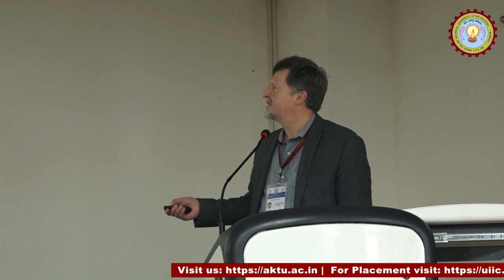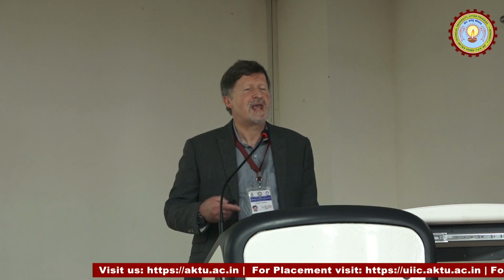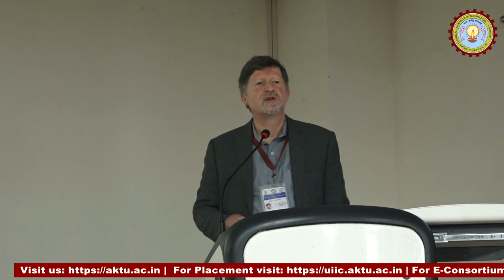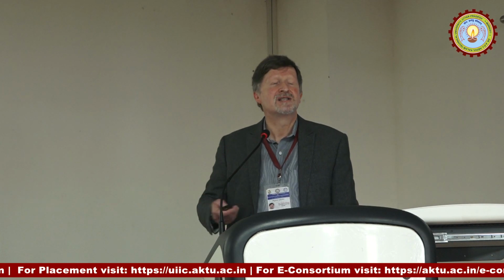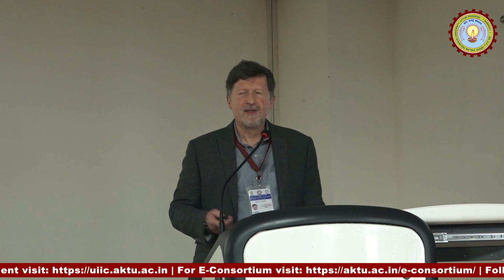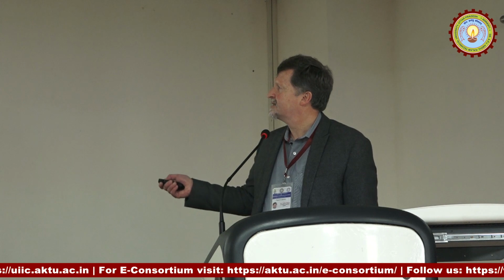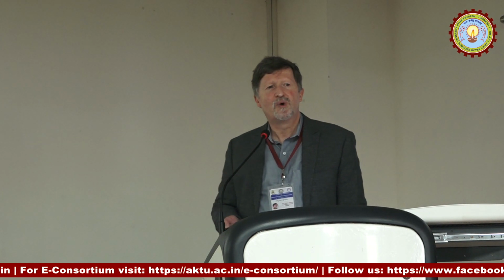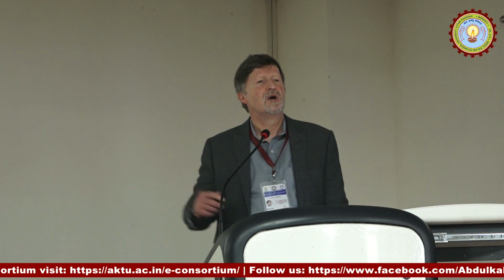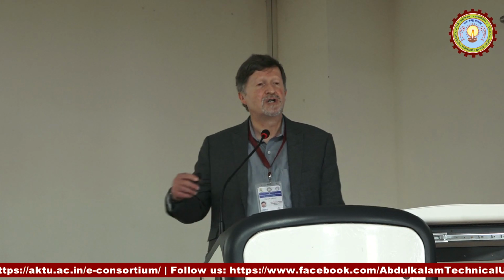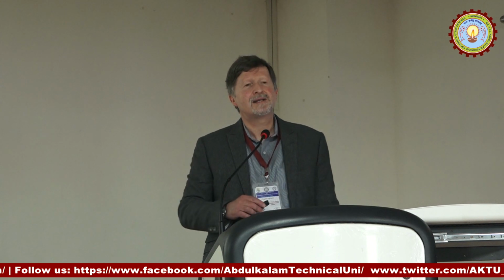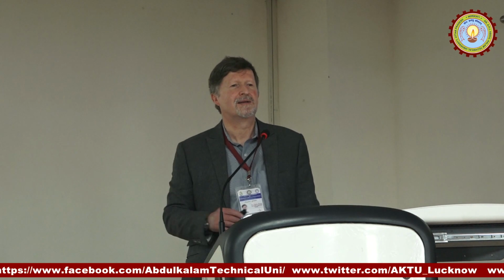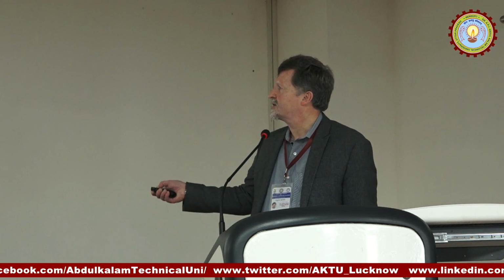And so we've moved to a cone beam spectroscopic type approach, where we actually use the energy of the detected photons to try to overcome some of the challenges that we face with a pencil beam approach. And this is done by going to a more complex CT reconstruction approach, where instead of using straight lines, which typically is what we've done in most traditional CT mechanisms, where we look at the source and the detector and we reconstruct along a single line, we're looking at arcs.